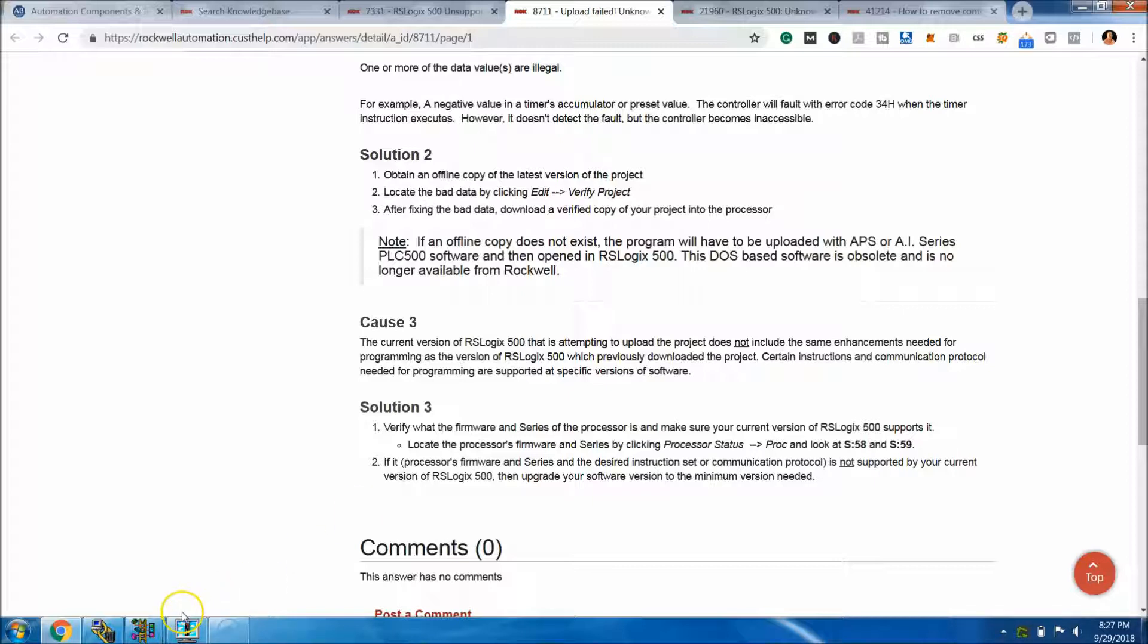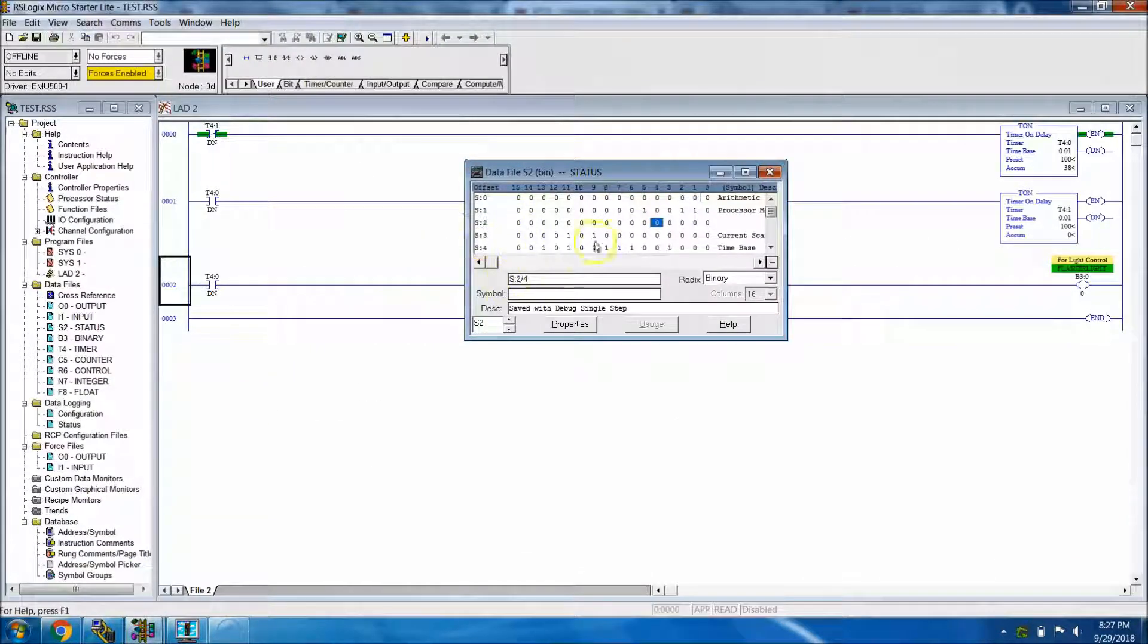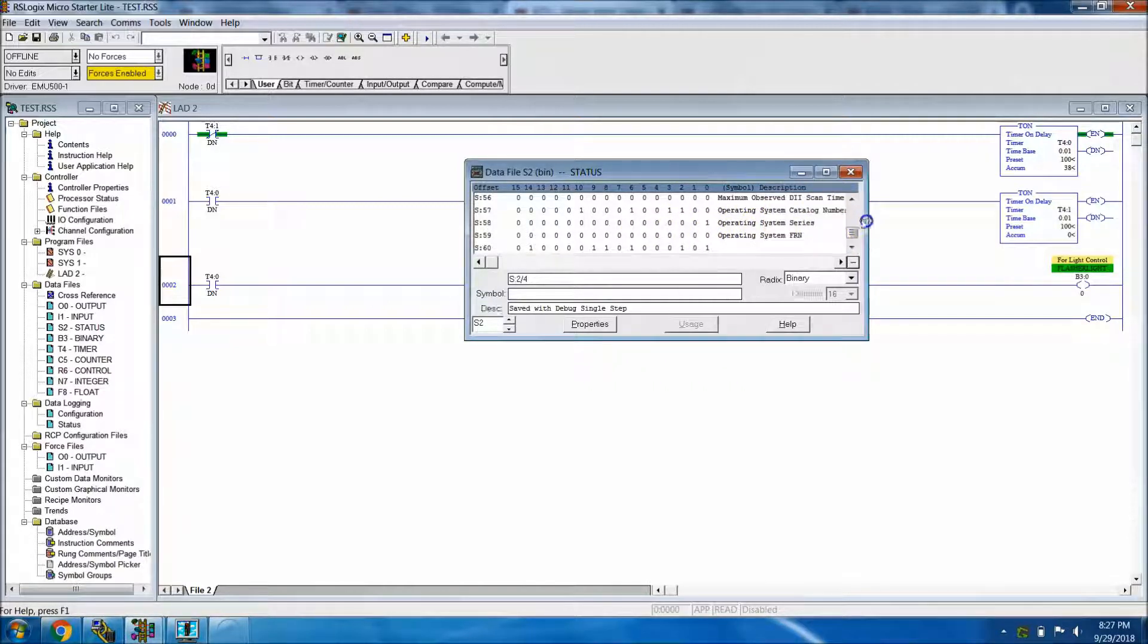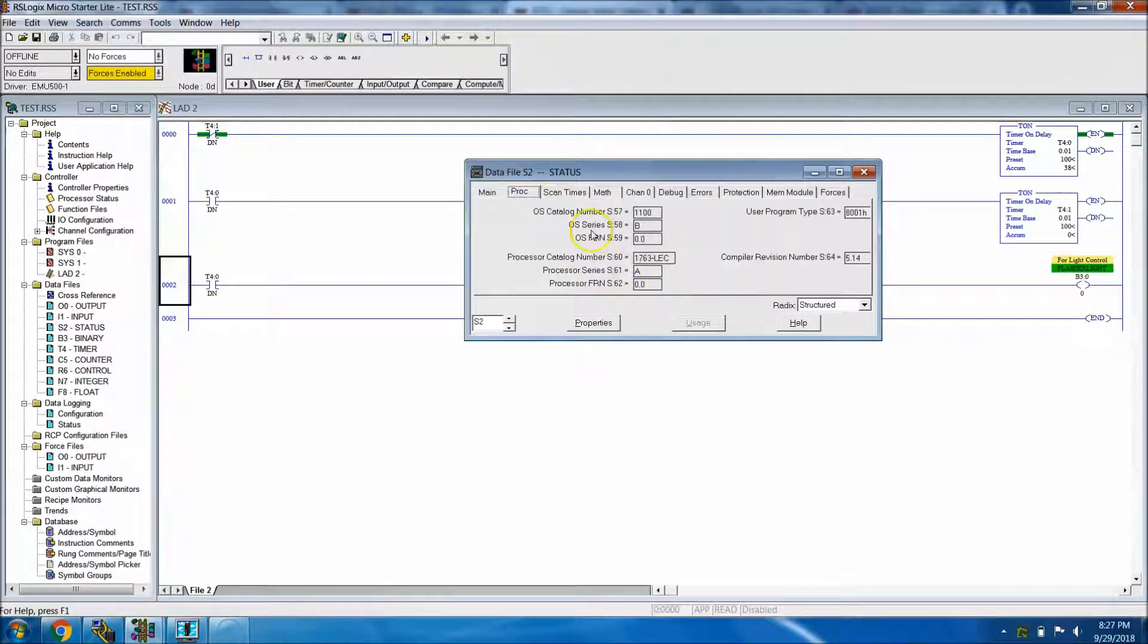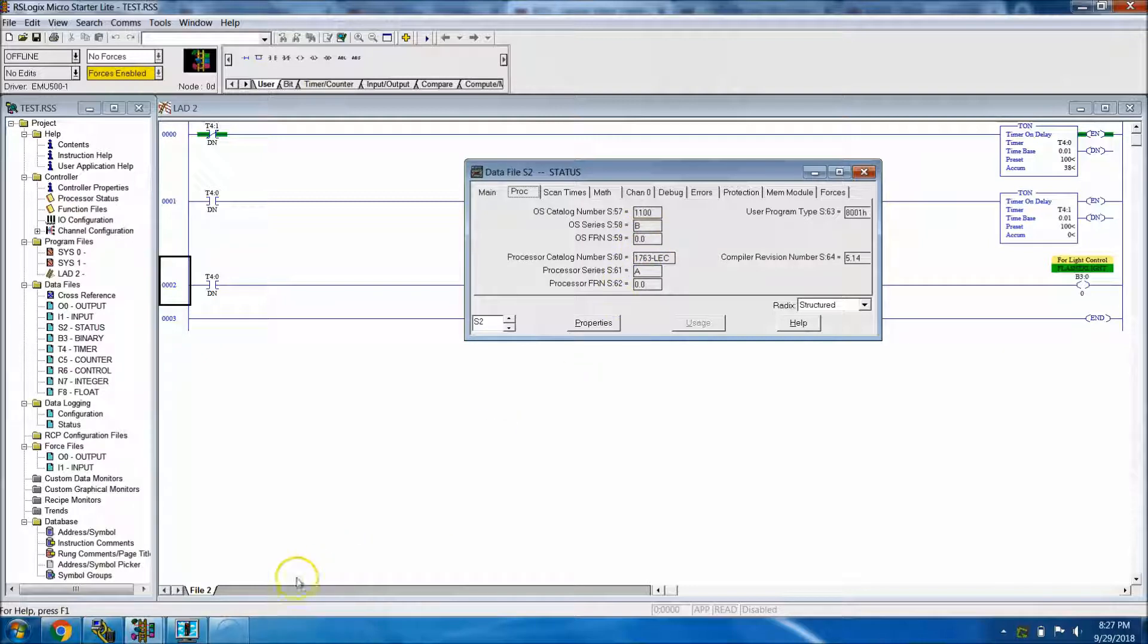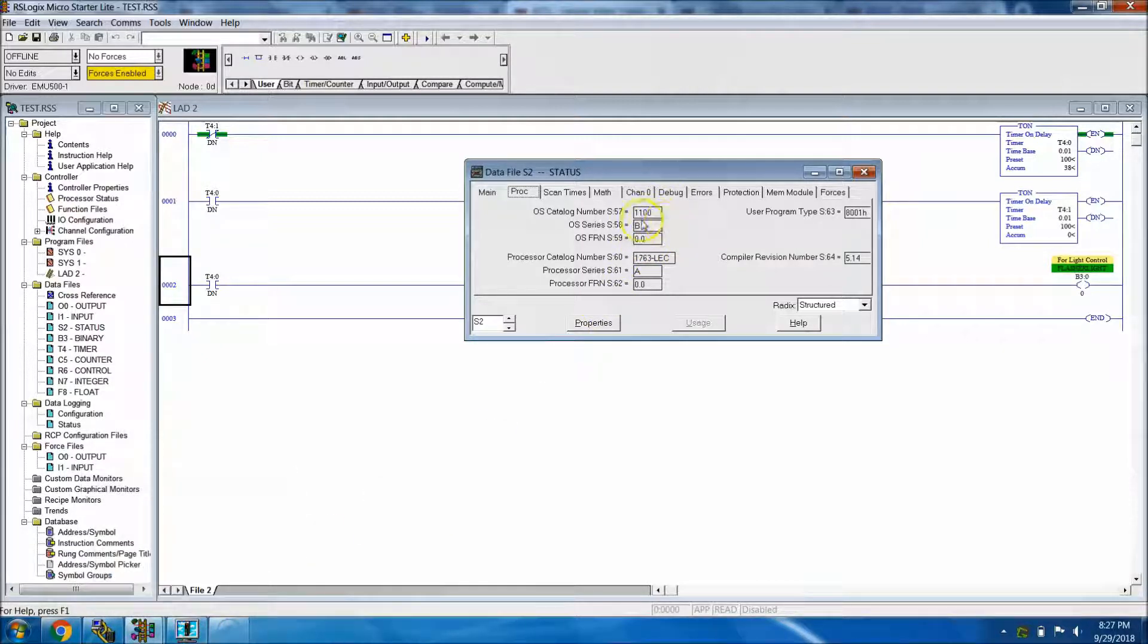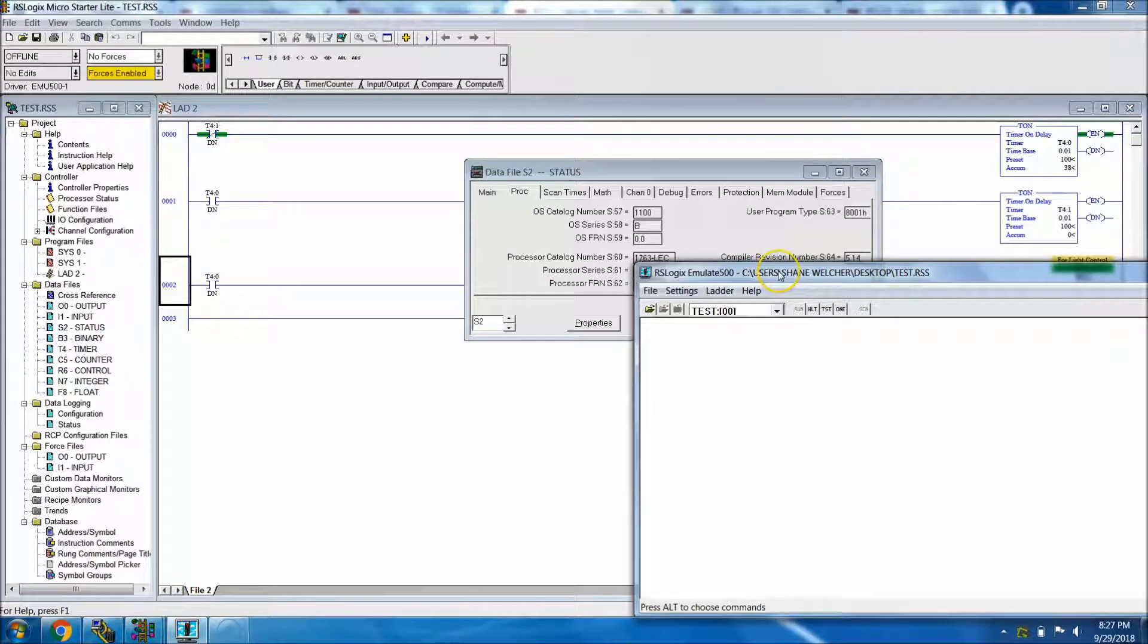In this case, if the two aren't lined up, then you could have a problem. Let's actually look at that. Go to S:58 and S:59. You can go right here and look at that series. You can see that this is a 1100 and it's series B. So if you're somehow you chose to use a different series or you choose to use a firmware that's not supported with the emulator, basically the RSLogix Emulate 500, you will then have a problem.